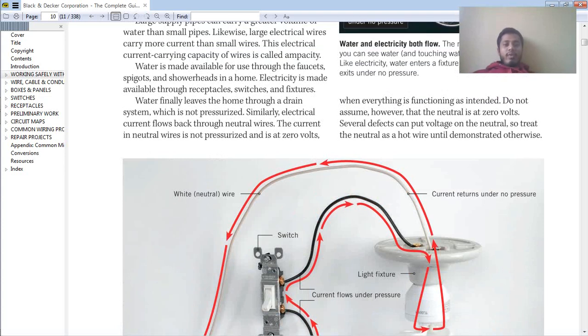When everything is functioning as intended, you might assume the neutral is at 0 volts - but do not assume that. Several defects can put voltage on the neutral, so treat the neutral as a hot wire until demonstrated otherwise.